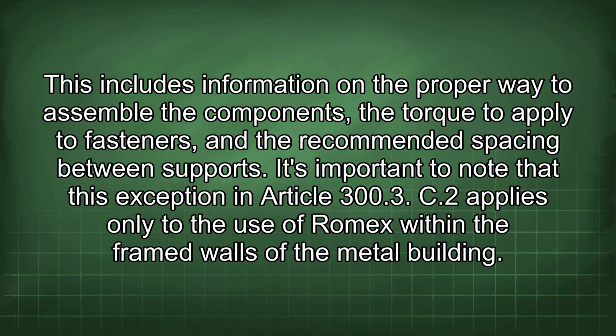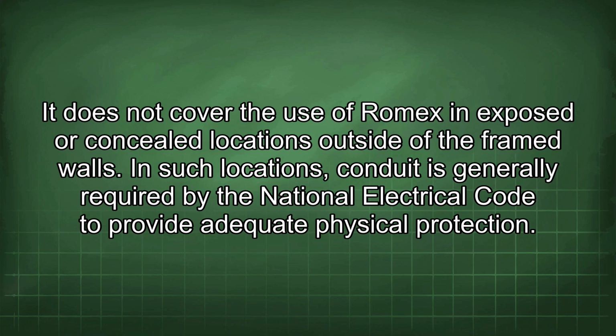It's important to note that this exception in Article 300.3 C2 applies only to the use of Romex within the framed walls of the metal building. It does not cover the use of Romex in exposed or concealed locations outside of the framed walls. In such locations, conduit is generally required by the National Electrical Code to provide adequate physical protection.